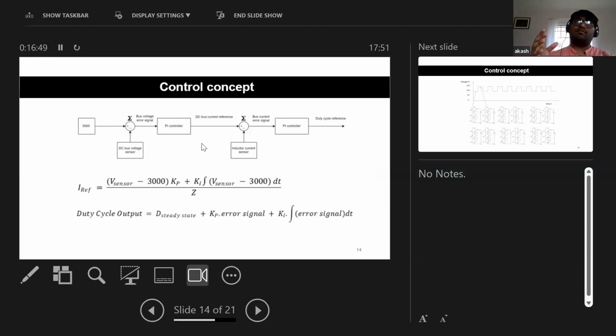The current going across the inductor is a function of the difference between the voltage stacking of the supercapacitors and the voltage on the DC bus. That then informs the second loop about what duty cycle you need to provide so that you keep the voltage at the 3 kilovolt level. The formulas here give an idea of how to set the PI parameters within the controllers — at least the first step, and after that you do a bit of tuning.